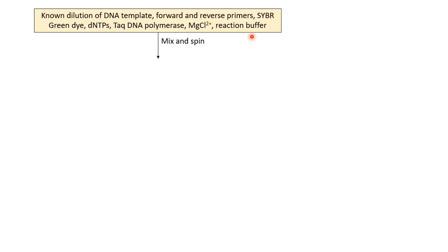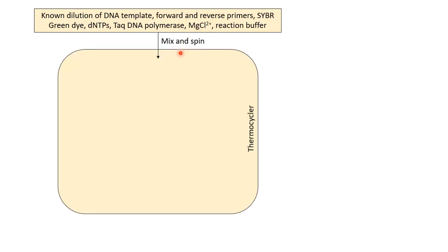After preparing the reaction mixture in a tube, it is mixed by vortexing and flash-spun for a few seconds to settle the content. The settled content in the tube is then placed in a real-time machine having a thermal cycler where temperature cycles at different ranges.